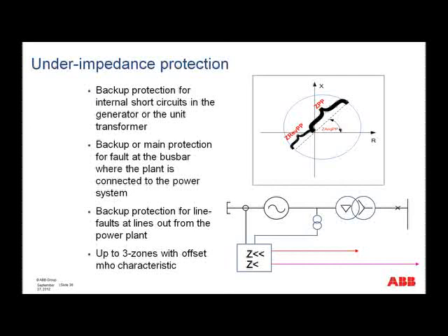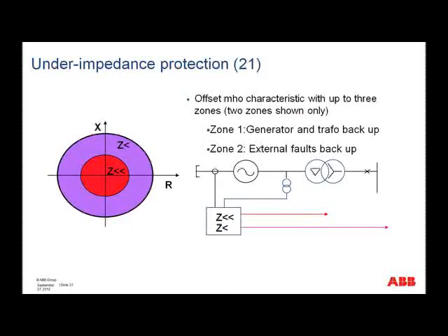Backup or main protection for fault at the bus bar, where the plant is connected to the power system. So of course if it was intended as main protection, probably then the bus bar would not have bus bar protection. But if the bus bar did have bus bar protection, then it would be backup to that. Backup protection for line faults at lines out from the power plant. And then you could have a number of zones, okay, and you could then play with these zones with the reach settings and with the time delays you give them to get the protection that you want.